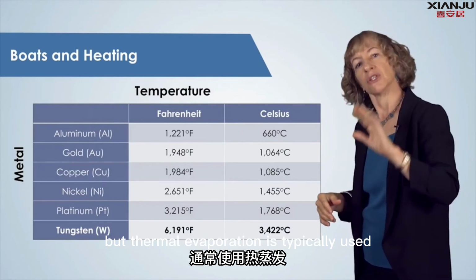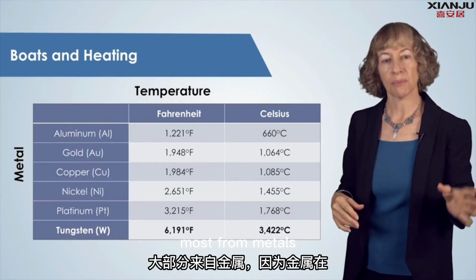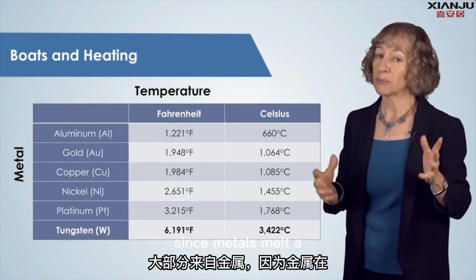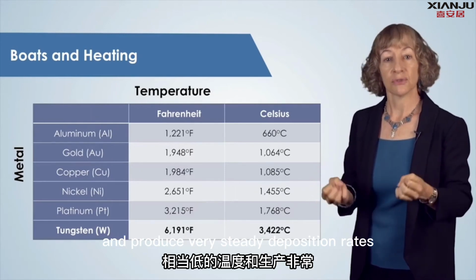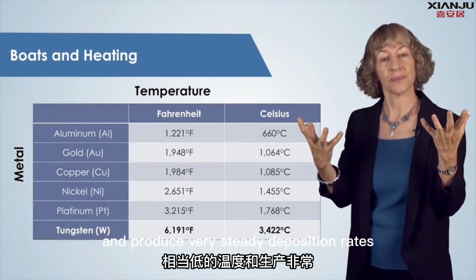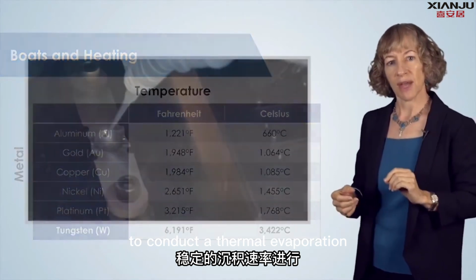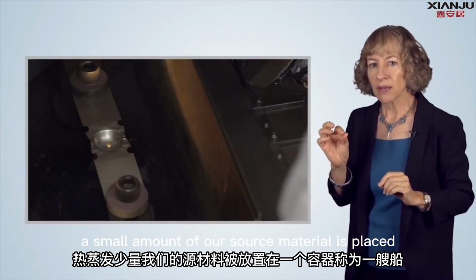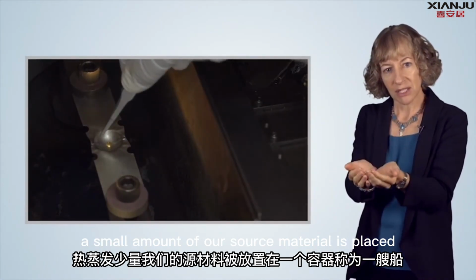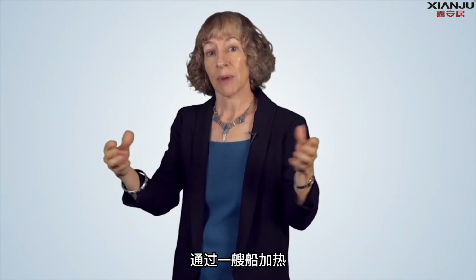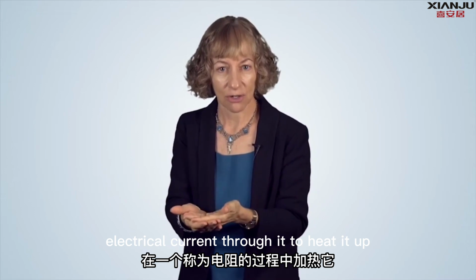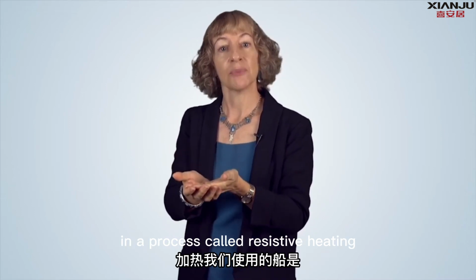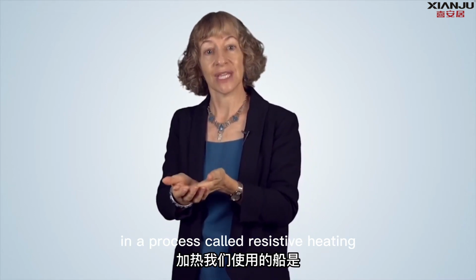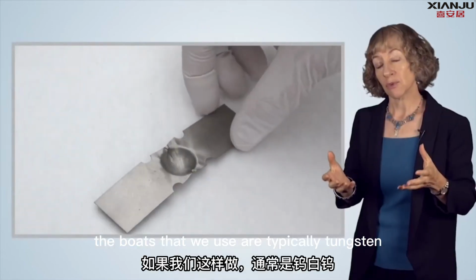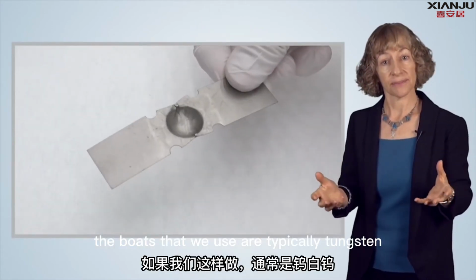But thermal evaporation is typically used most for metals, since metals melt at pretty low temperatures and produce very steady deposition rates. To conduct a thermal evaporation, a small amount of our source material is placed into a container called a boat. The boat is heated by passing a large electrical current through it to heat it up in a process called resistive heating. The boats that we use are typically tungsten.